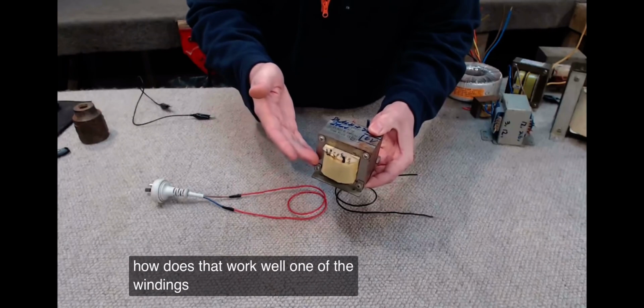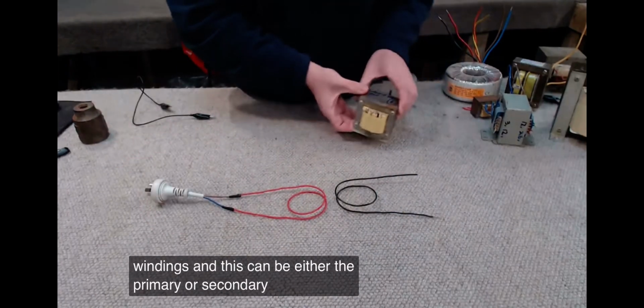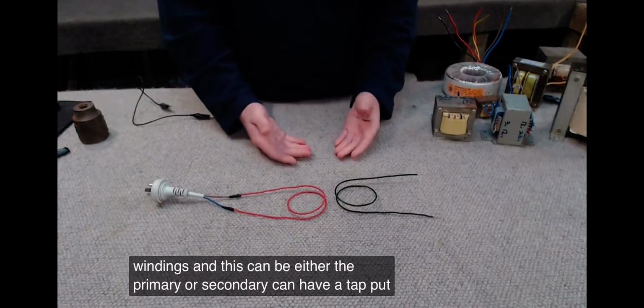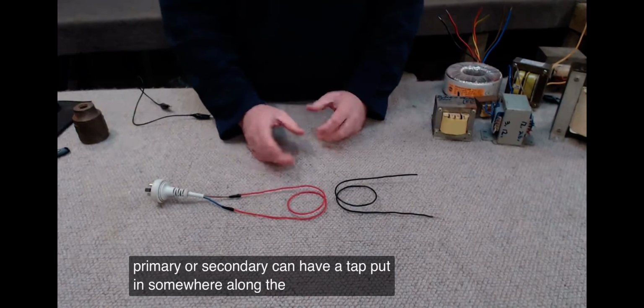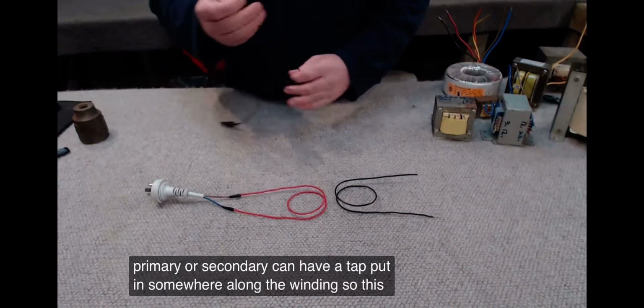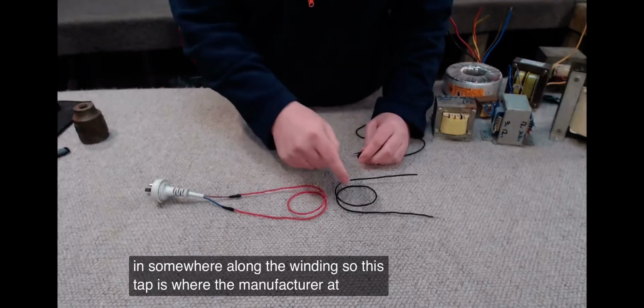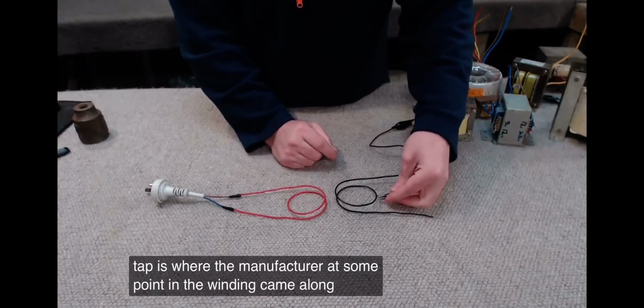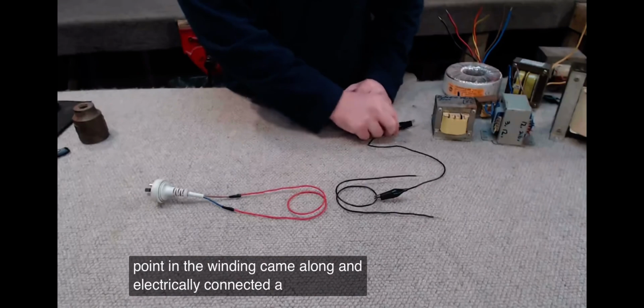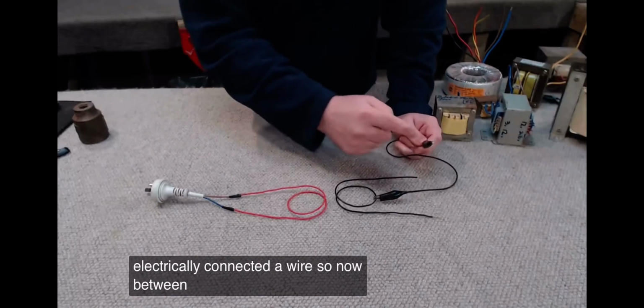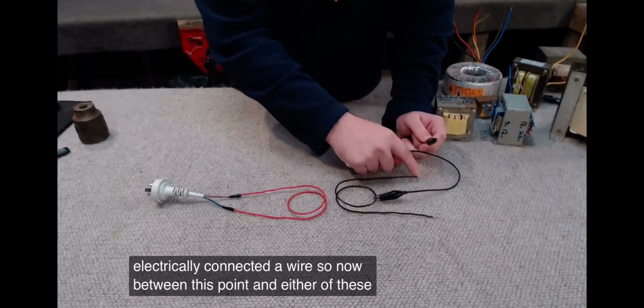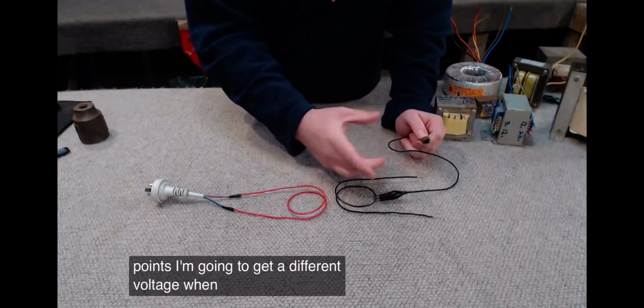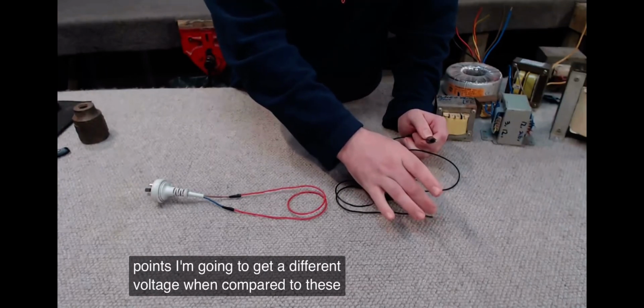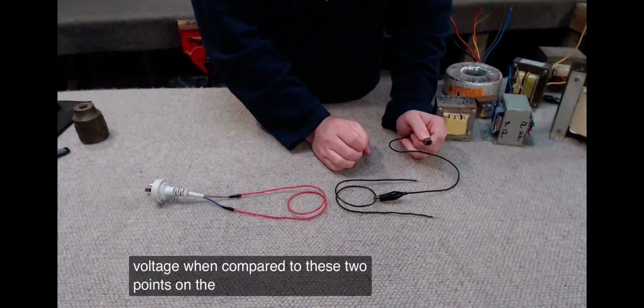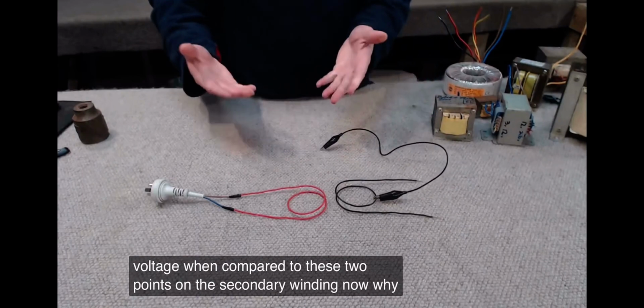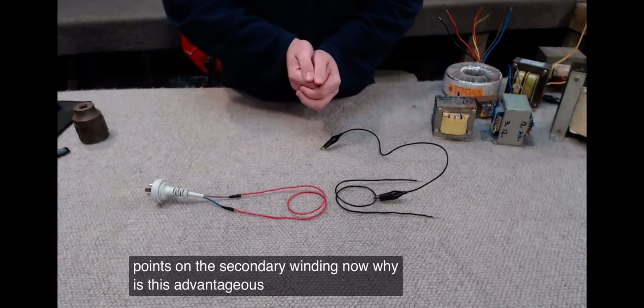Well, one of the windings, and this can be either the primary or secondary, can have a tap put in somewhere along the winding. A tap is where the manufacturer at some point in the winding came along and electrically connected a wire. So now between this point and either of these points I'm going to get a different voltage when compared to these 2 points on the secondary winding. Now, why is this advantageous?